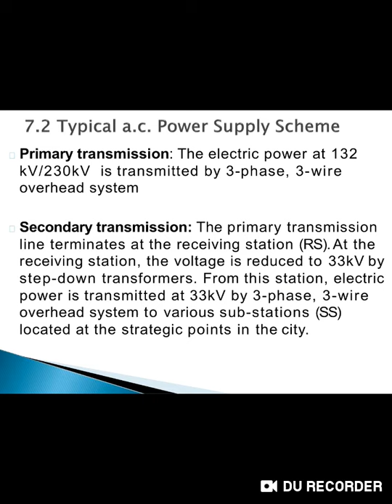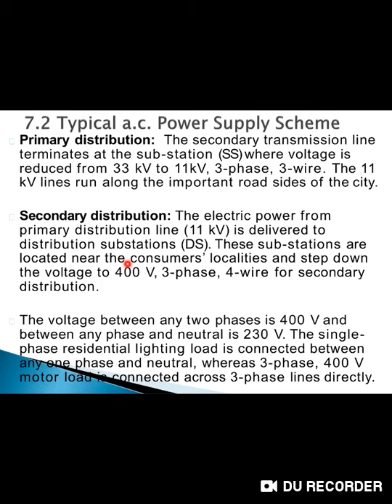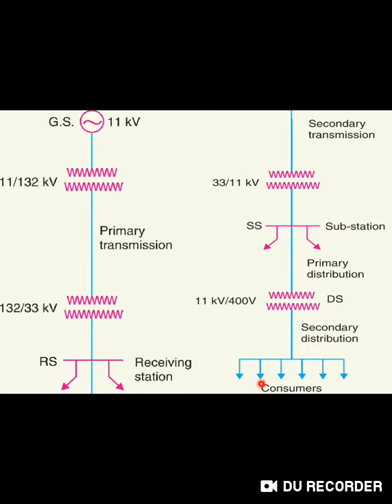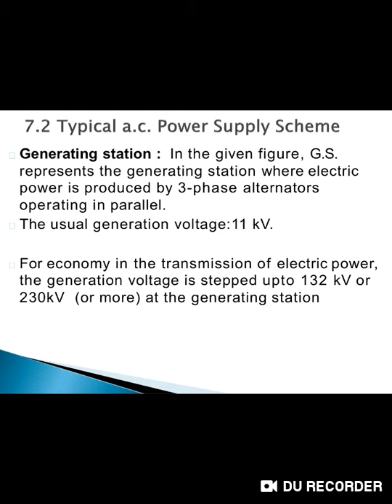Next, secondary distribution. The electric power from the primary distribution line, that is 11 kV, is delivered to distribution substations. These substations are located near the consumers. This is the secondary distribution. Whenever the primary distribution terminates at the distribution substations, the 11 kV voltage is reduced to 400 volts by using step-down transformers. These distribution substations are located near the consumers. We are the consumers. This is the secondary distribution.